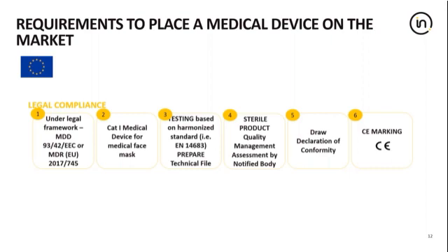So what are the steps which would be necessary to CE mark a medical mask? We've seen on the previous slide that they come under the legal framework of the Medical Devices Directive or the Medical Devices Regulation and are classed as a Category 1 medical device. This means that any testing program should be based on the harmonised standard EN 14683. A technical file should be prepared to cover the essential requirements of the legislation. And a technical file is something which is similar to a product specification, but includes aspects to assess the risk management process. And the testing process and test reports should be included as part of that technical file.